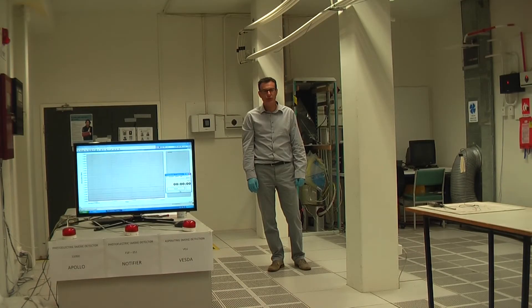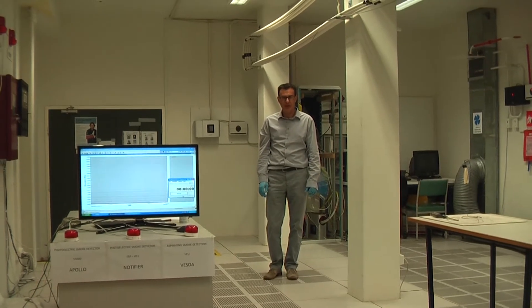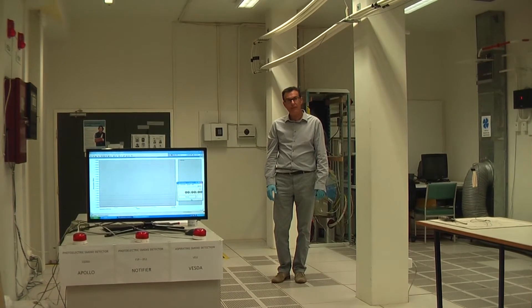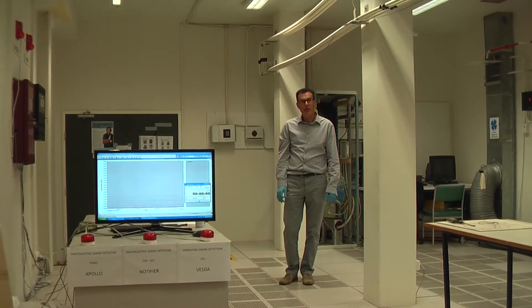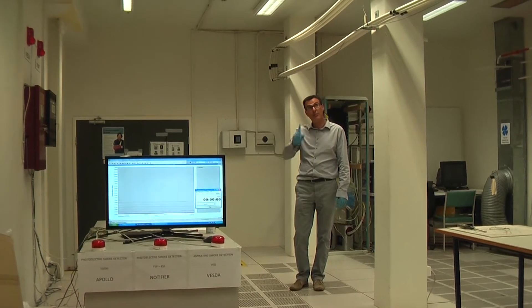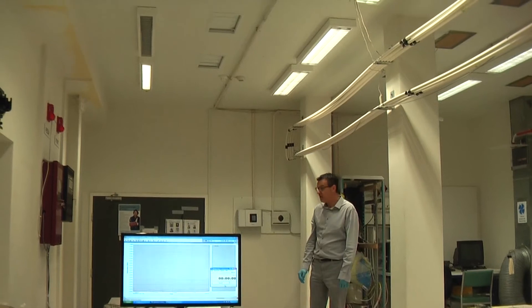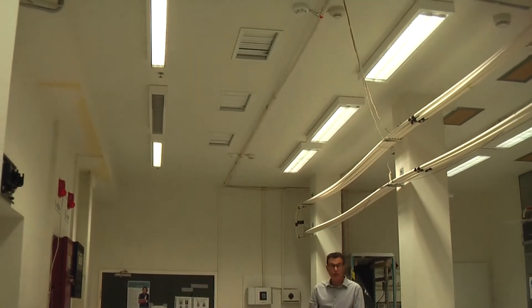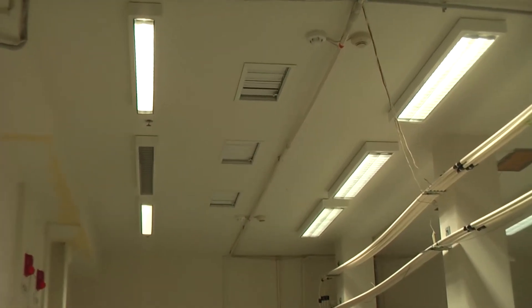This demonstration is a small protection comparison between ASD and spot protectors. In a room of 60 square meters with a high ceiling, protection systems are mounted underneath the ceiling. The assessment is between a VESDA detector and two spot detectors: the first one is an Apollo and the second one a Notifier.